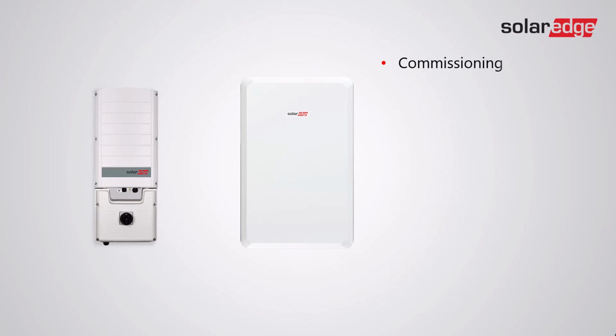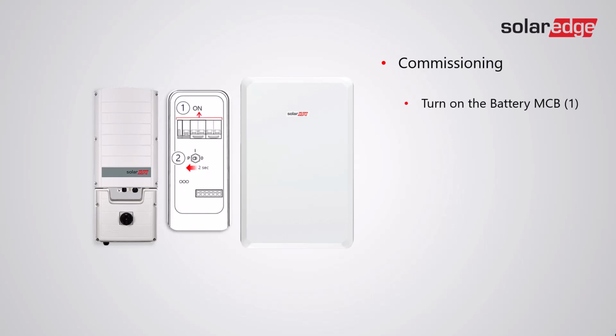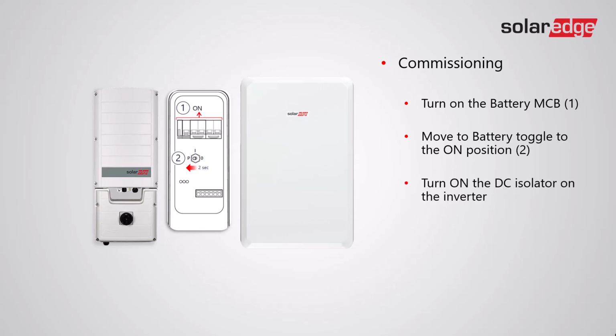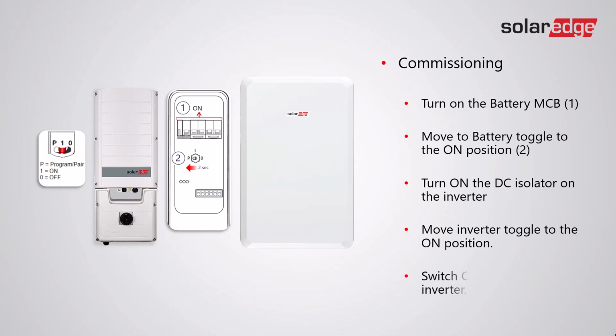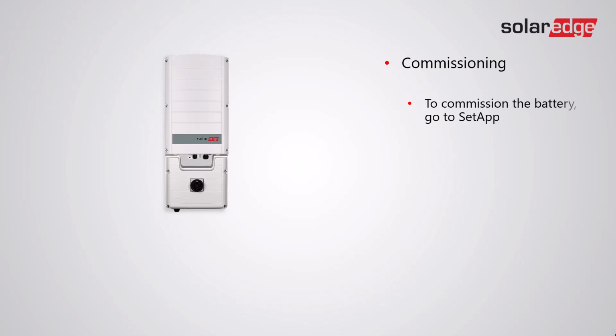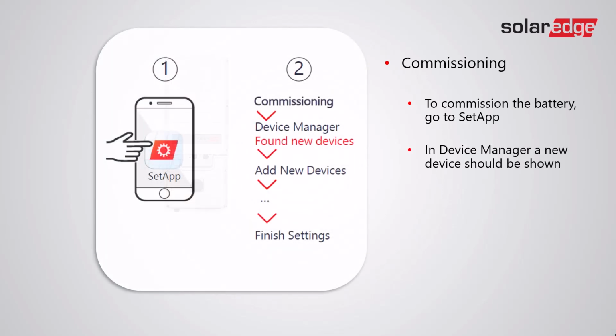For commissioning, turn on the battery MCB, move the battery toggle to the on position, turn on the DC isolator on the inverter, move the inverter toggle to the on position, then switch on the AC to the inverter. To commission the battery, go to SetApp. In Device Manager a new device should be shown. Follow the guided prompts to set up the battery.